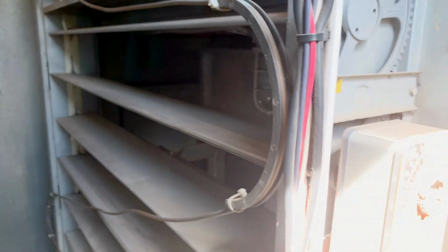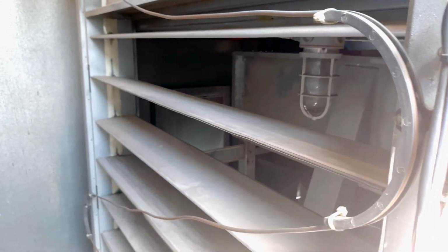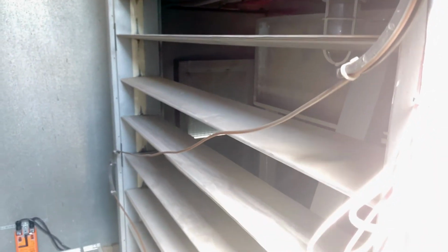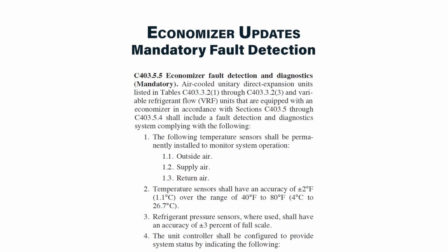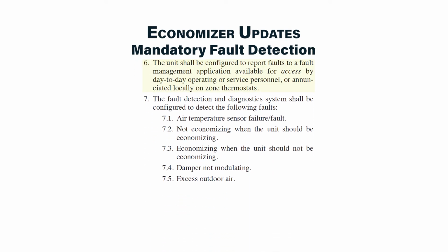The last economizer update I want to talk about is mandatory fault detection. Economizers can use a lot more energy than intended if they're not running properly due to poor sensor calibration or broken dampers or valves. The requirement just says that every economizer system needs to have fault detection to alert building operators to make repairs on the system.